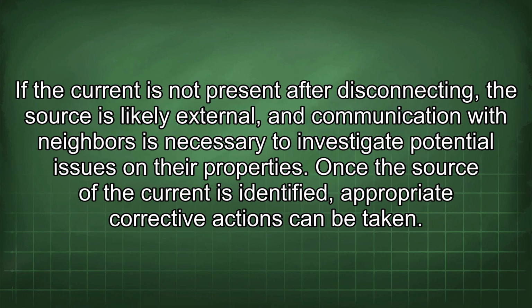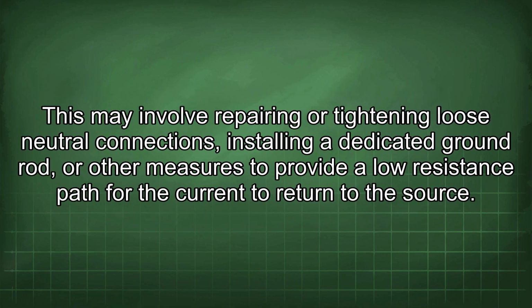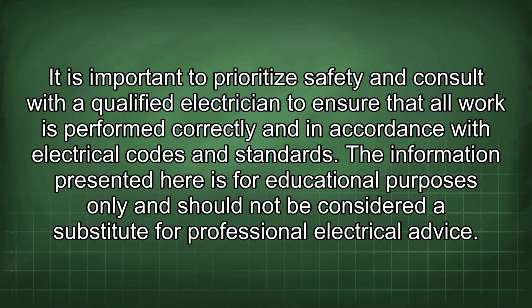If the current is not present after disconnecting, the source is likely external, and communication with neighbors is necessary to investigate potential issues on their properties. Once the source of the current is identified, appropriate corrective actions can be taken. This may involve repairing or tightening loose neutral connections, installing a dedicated ground rod, or other measures to provide a low resistance path for the current to return to the source. It is important to prioritize safety and consult with a qualified electrician to ensure that all work is performed correctly and in accordance with electrical codes and standards.